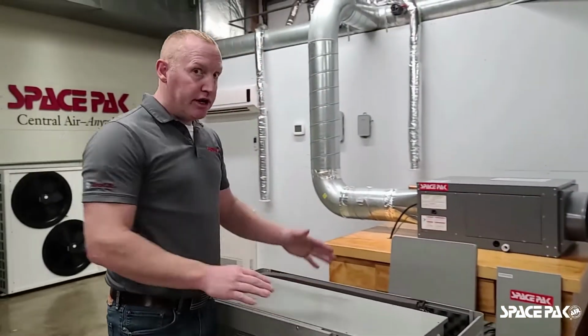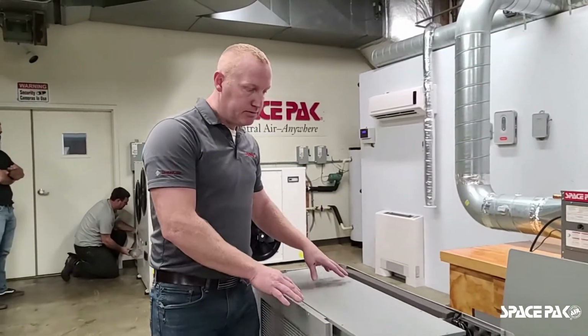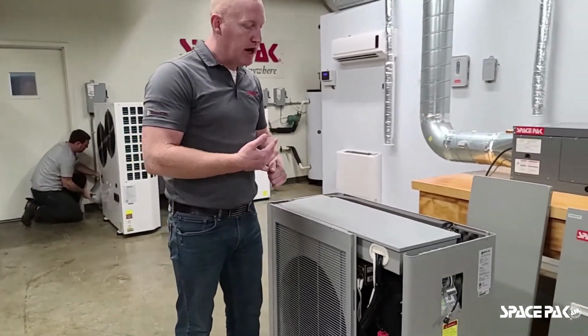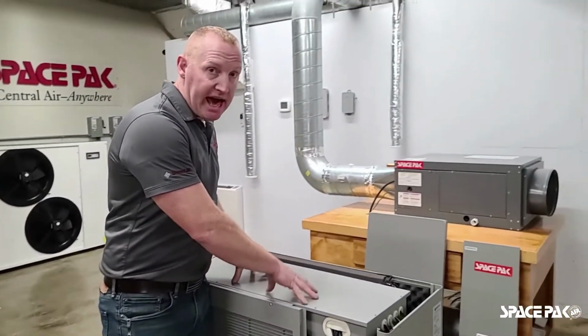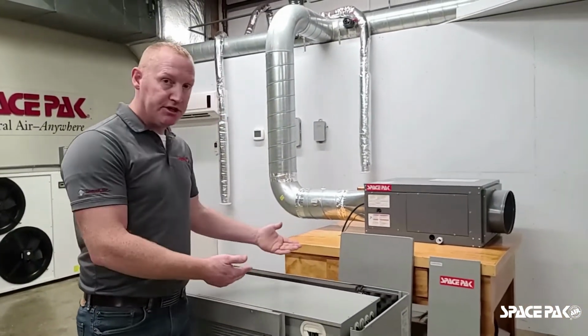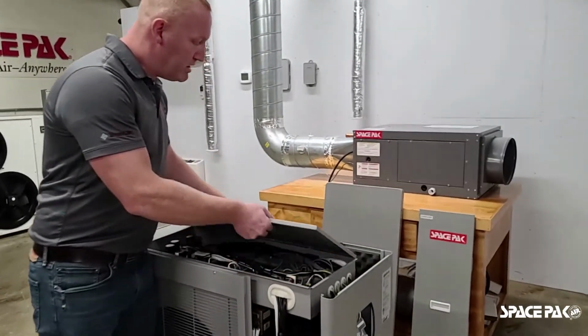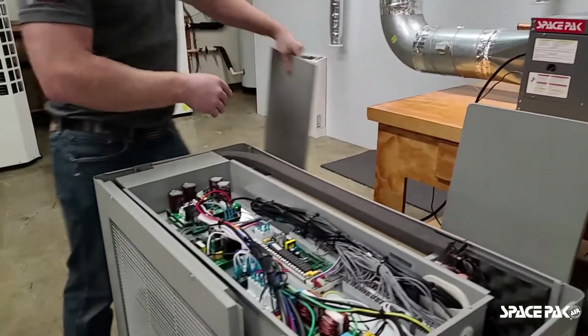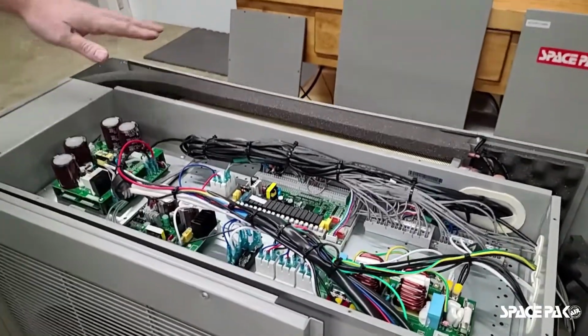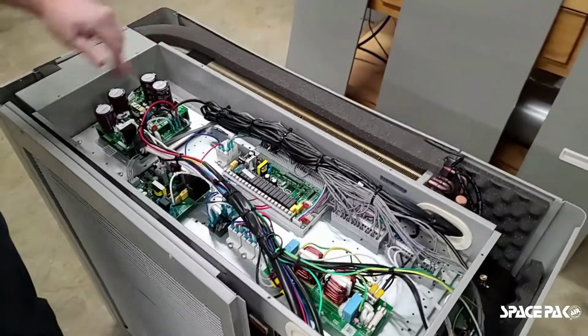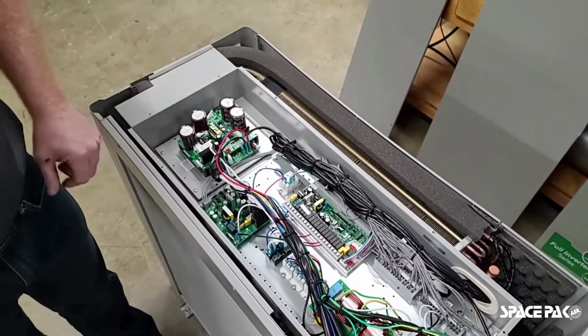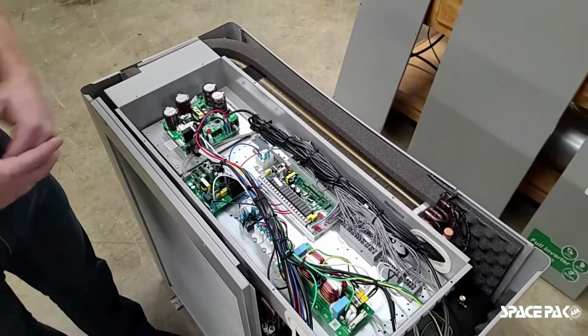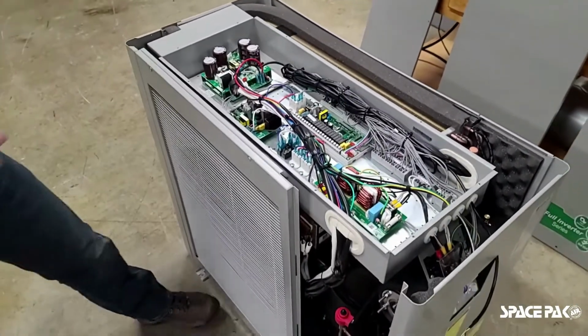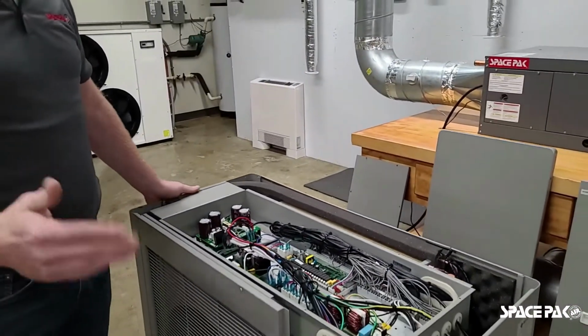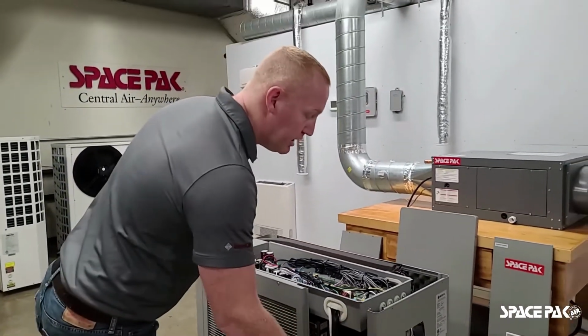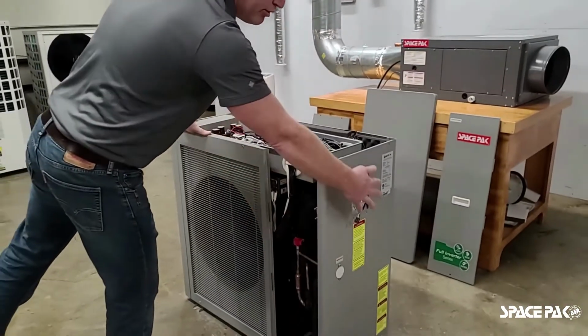Going a little deeper, now under general control, general installation situations, normal contracting, basic installations will not have to access this part of the system up front. However, it's important to show you what's in here. We take this cover off and we kind of get into the brains of the operation as well. We have a few more connections available at different times if required, control boards and things of that nature. It's up here, relatively out of the way, nice and clean and neat. But as mentioned, anything that we need to get to for our basic installations and upfront commissioning can be accessed either through the front or through the electrical side panel.